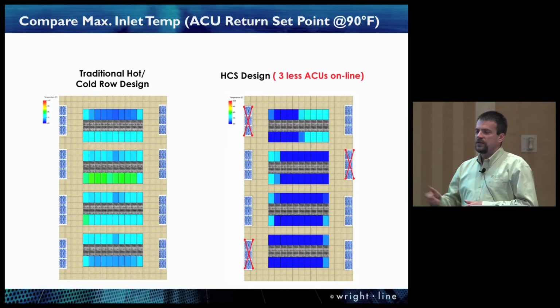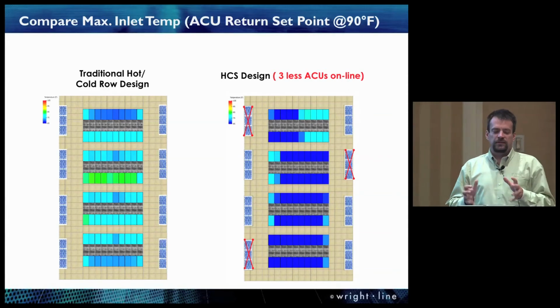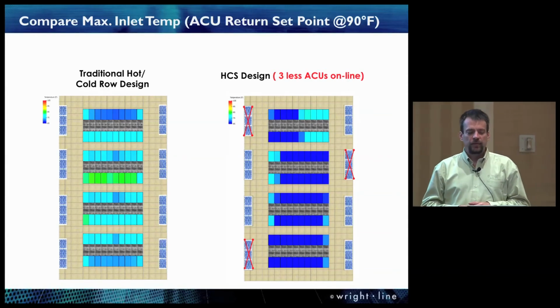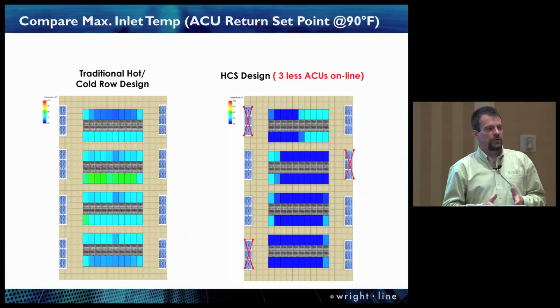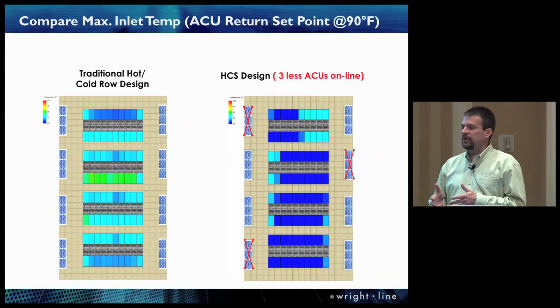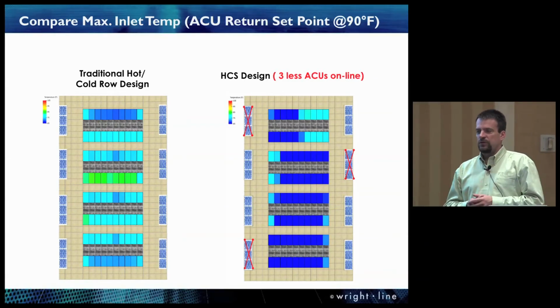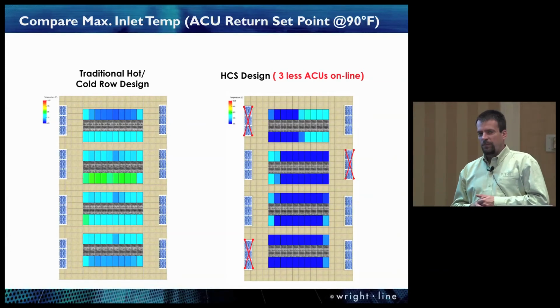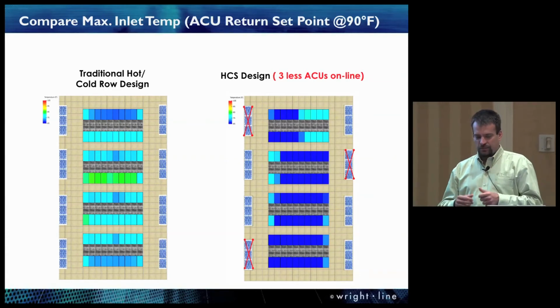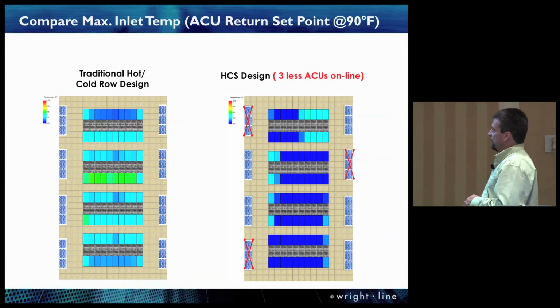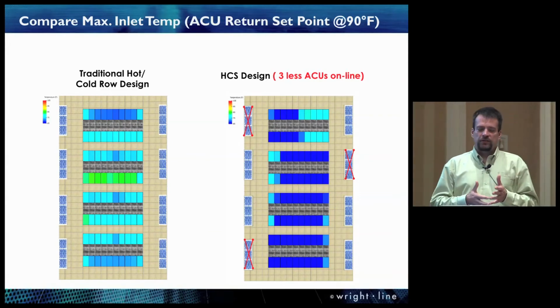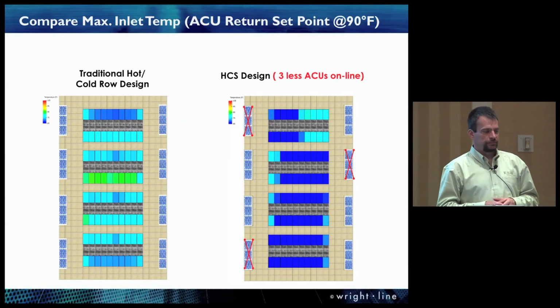So really what you're seeing here is 8 CRAC units to be able to get this traditional data center up and operational, and all racks are reporting acceptable inlet temperatures within the ASHRAE range. And this is just one part of a CFD. We can get in a lot deeper, but as you look on the chimney type side, you can see 3 CRACs have actually been taken offline.